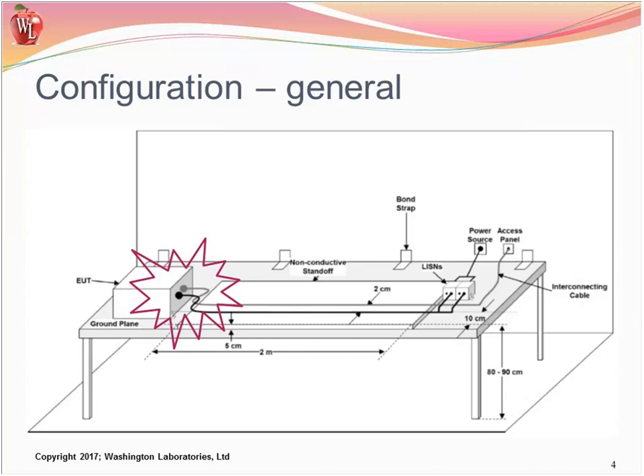Configuration things in general have changed somewhat, shall we say. We notice that in the star there that I'm showing, it indicates that the cables tend to come out the side. A lot of people have indicated that that is the desired position simply from the diagram. Well, the standard doesn't support that in the text. The standard says you need to orient for the maximum signal, emissions, or vulnerability. So cable routing could be significant, where the connector may need to be pointed towards the antenna.